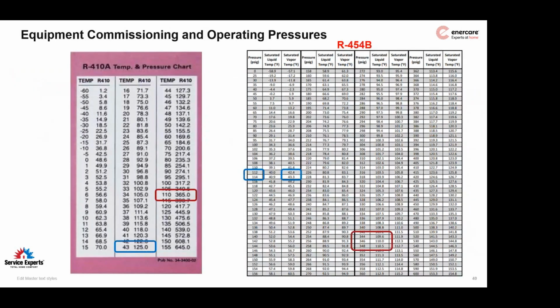Oftentimes when we switch refrigerants, there is some concern that the pressures are going to be different. I've already hinted that the pressures are going to be very similar. But there is a key difference with R454B that wasn't as prominent in 410A, and they never had to identify it on their pressure temperature charts. R454B has 2.5-ish degrees of glide between its vapor state and its liquid state for saturation temperatures. 410A actually has a degree and a half of glide, but they never actually charted it.